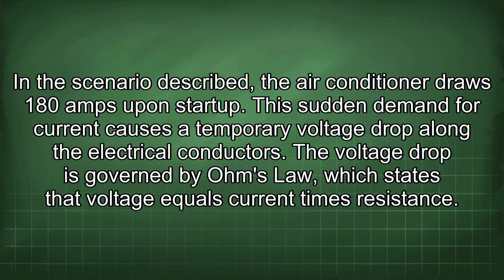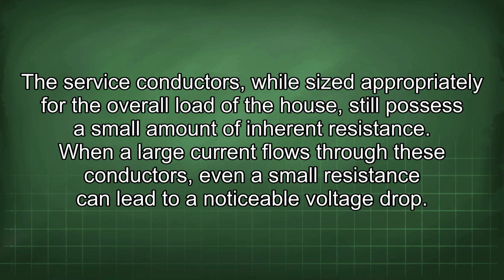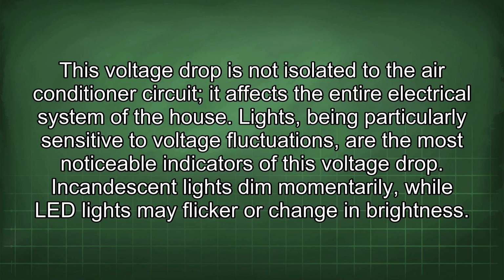This sudden demand for current causes a temporary voltage drop along the electrical conductors. The voltage drop is governed by Ohm's law, which states that voltage equals current times resistance. The service conductors, while sized appropriately for the overall load of the house, still possess a small amount of inherent resistance. When a large current flows through these conductors, even a small resistance can lead to a noticeable voltage drop. This voltage drop is not isolated to the air conditioner circuit, it affects the entire electrical system of the house.